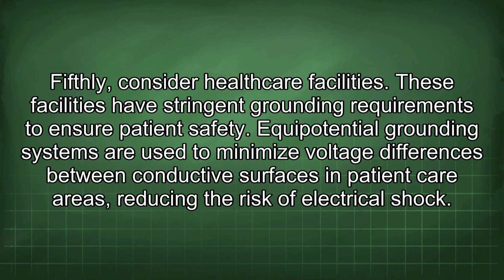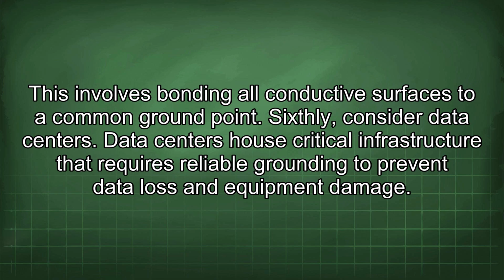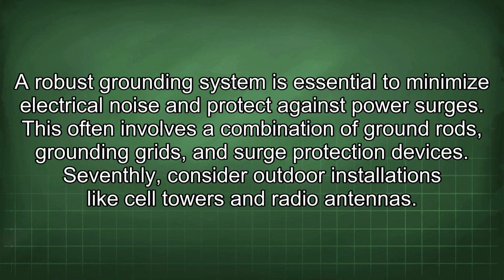Fifthly, consider healthcare facilities. These facilities have stringent grounding requirements to ensure patient safety. Equipotential grounding systems are used to minimize voltage differences between conductive surfaces in patient care areas, reducing the risk of electrical shock. This involves bonding all conductive surfaces to a common ground point. Sixthly, consider data centers. Data centers house critical infrastructure that requires reliable grounding to prevent data loss and equipment damage. A robust grounding system is essential to minimize electrical noise and protect against power surges. This often involves a combination of ground rods, grounding grids, and surge protection devices.